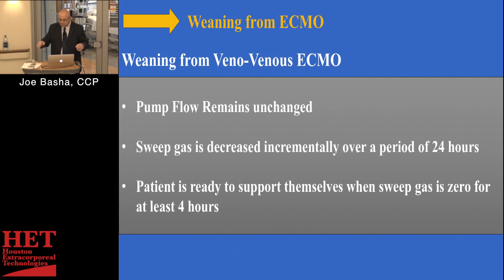So you can wean those patients just by controlling the sweep gas, or tidal volume if you will, and the FiO2, how much you're oxygenating that venous blood. Of course, you have to adjust your ventilator. You can't just leave the ventilator turned way down and turn this down and expect it to work. So the pressures are better, the patient's looking better, the x-ray looks better. Okay, we're going to go up on the ventilator, turn the FiO2 up from 40 to 60 maybe, and increase the tidal volume from 300 or 400 up to 600. They're looking better, pressures look better, and then you start weaning down your ECMO oxygenation portion and see how they look.